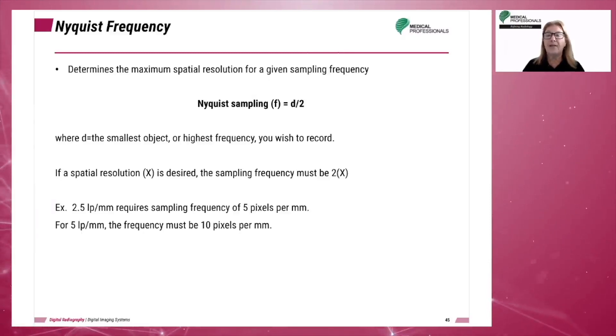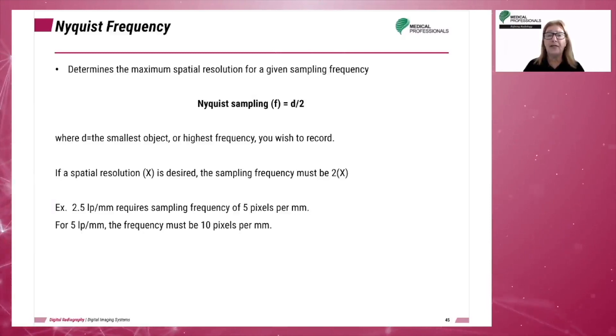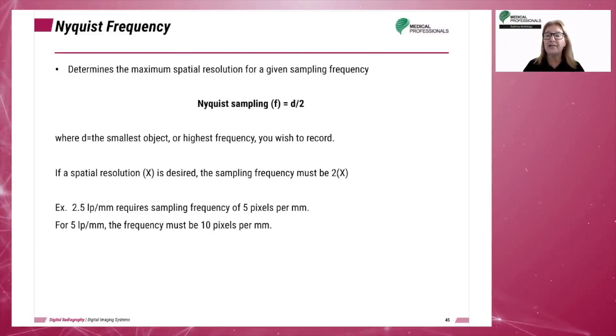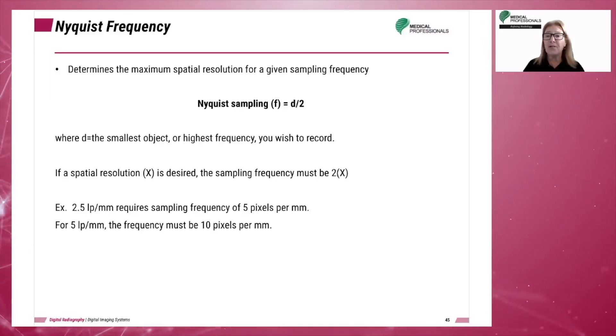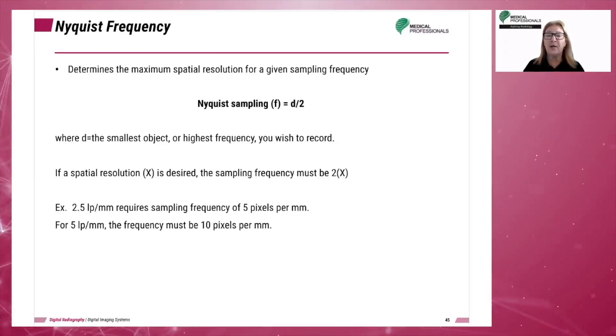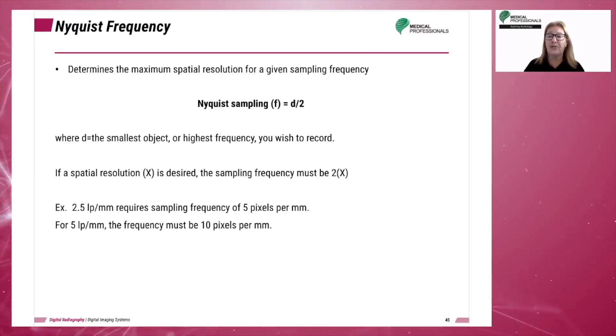The Nyquist theorem applies to computed radiography imaging. The Nyquist frequency determines the maximum spatial resolution for a given sampling frequency. The Nyquist theorem states that if spatial resolution, or x, is desired, the sample frequency must be 2 times x, or spatial resolution.